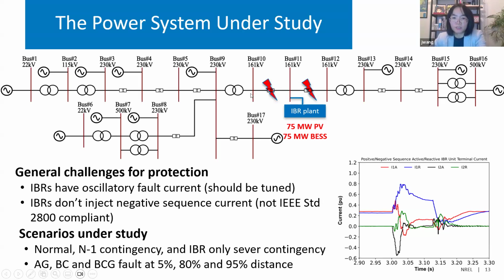So we need to do the first study for both lines as shown here. And for this PV and the BESS inverter, we have the preliminary study to see what the potential challenges are. First of all, the grid following and the grid forming inverter both have very low fault current, and the fault current is also very oscillatory, as you can see here. We talked to our vendor, they said this should be tuned in the future. And the more serious problem is both of them don't inject the negative sequence current. This will be a problem for the transmission protection elements that rely on the regulated negative sequence current. So those are the challenges there.